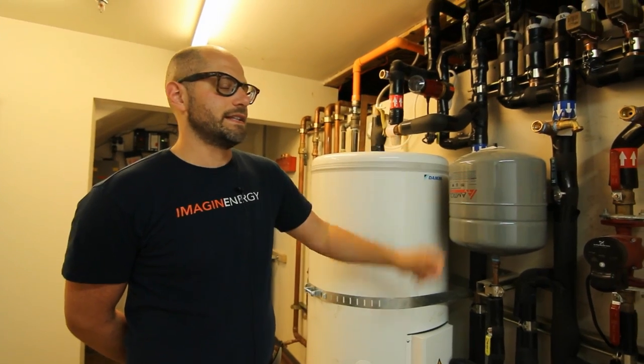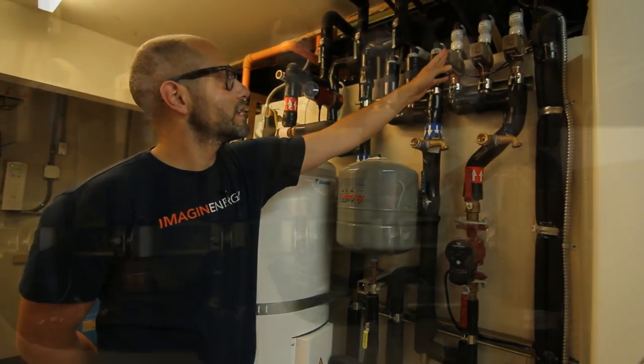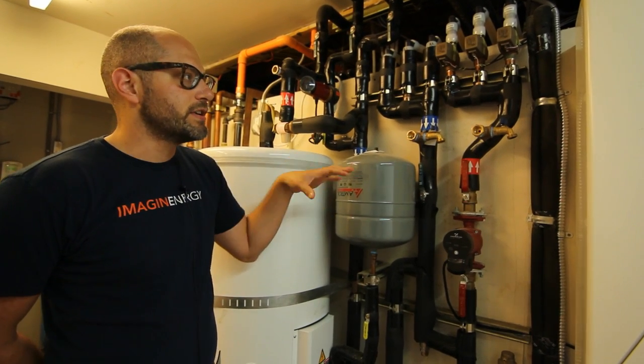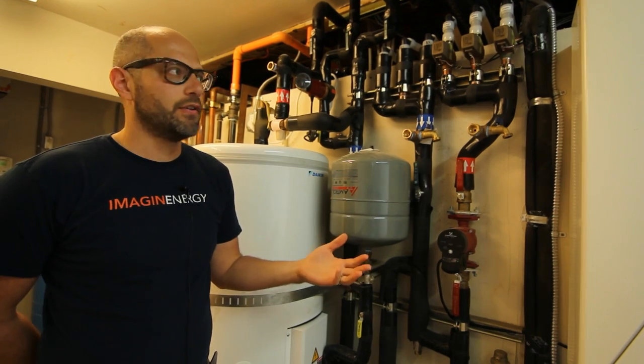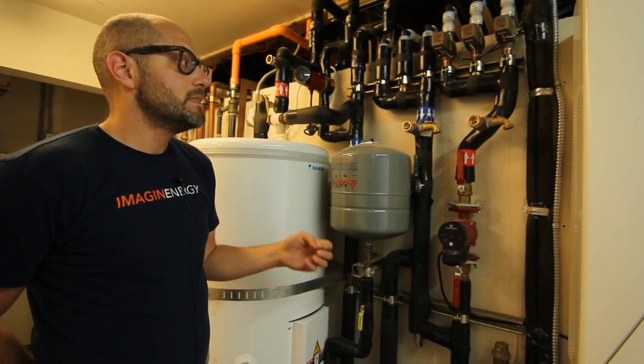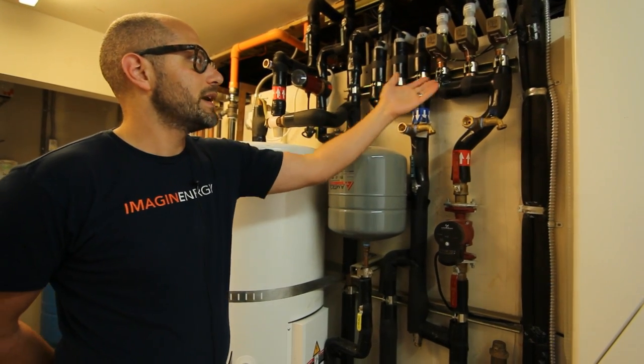We're looking at the radiant heating system at the Karuna house that provides tempering to the building through the floors. We actually have three different zones that you can see clearly right here. In a lot of homes with a radiant floor system and more typical construction they'll have six or eight different zones, because there are different needs in different parts of the building and the temperature is not always consistent. In a passive house temperatures are really even across surfaces, walls, windows and floors, so we're able to use a much simpler, more elegant system. Some passive houses might only have one zone, which works really well for big open spaces. In our case we have three distinct wings of the building, so we have three zones accordingly.